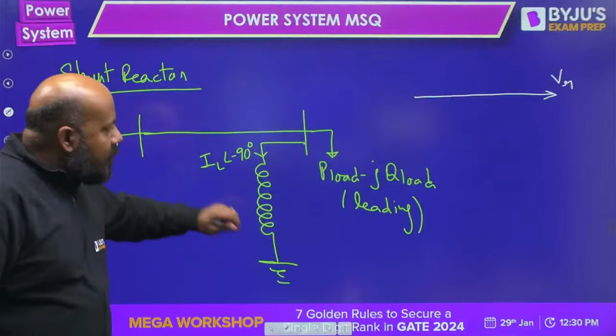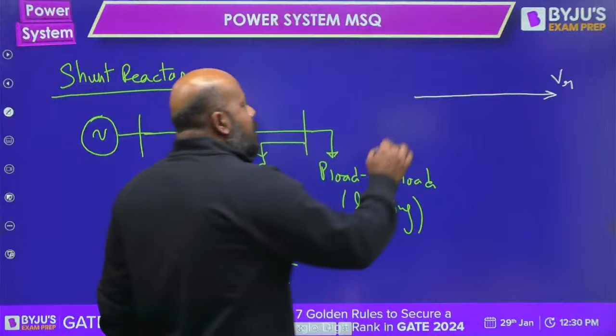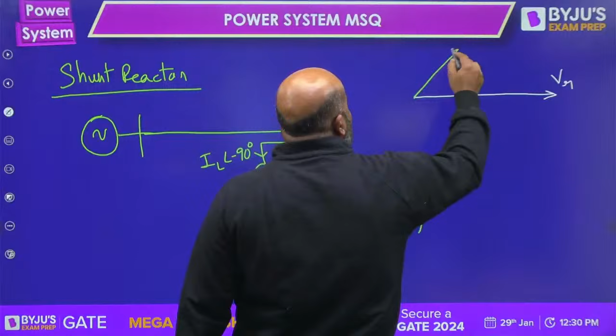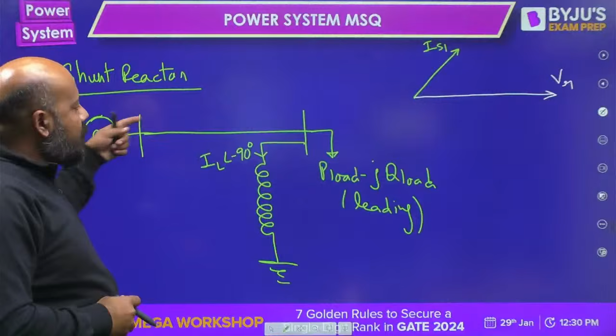Suppose this is the receiving end voltage. When the shunt reactor was not connected, it was a leading load, so the current drawn by the load was leading. Suppose the leading current is something like this. This was IS1, the current coming from the supply going to the load when the shunt reactor was not present.